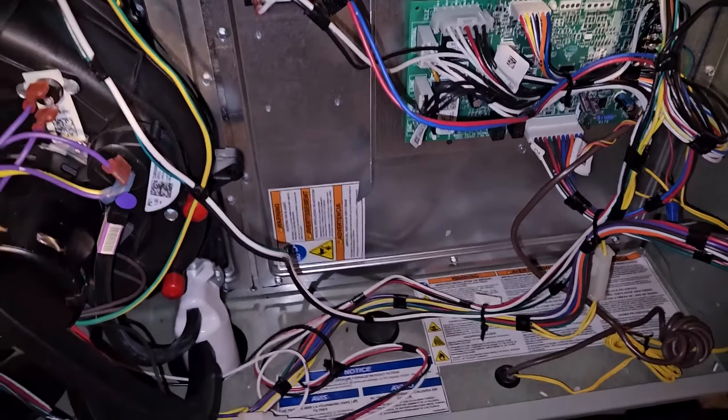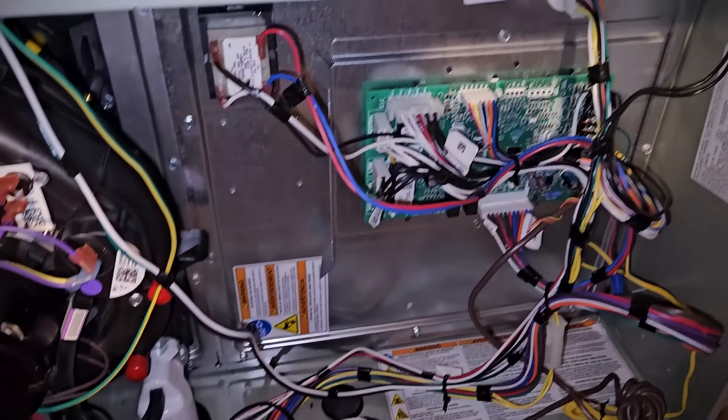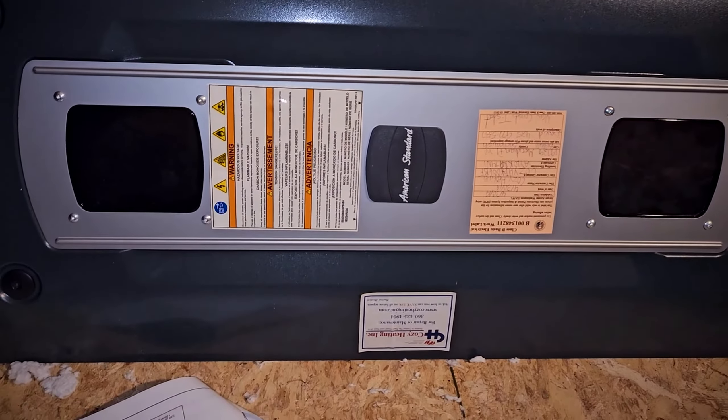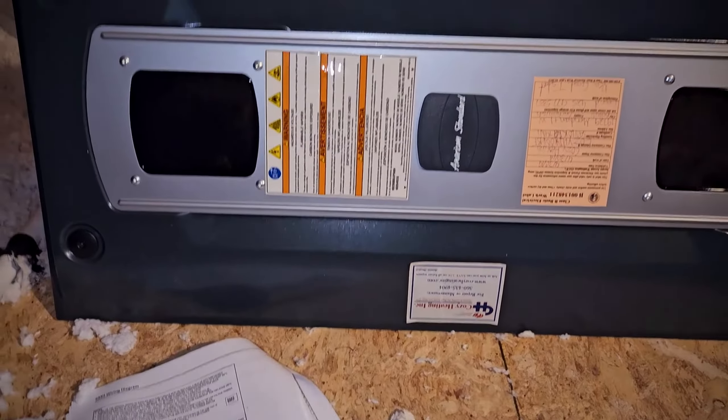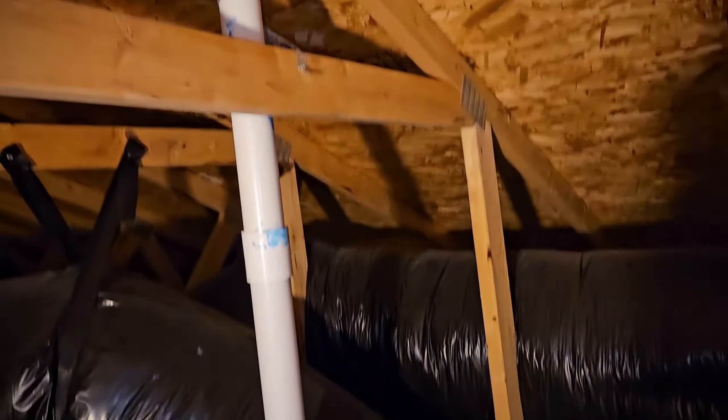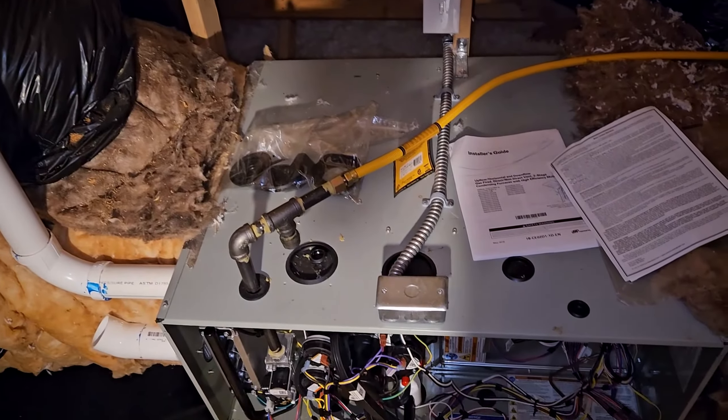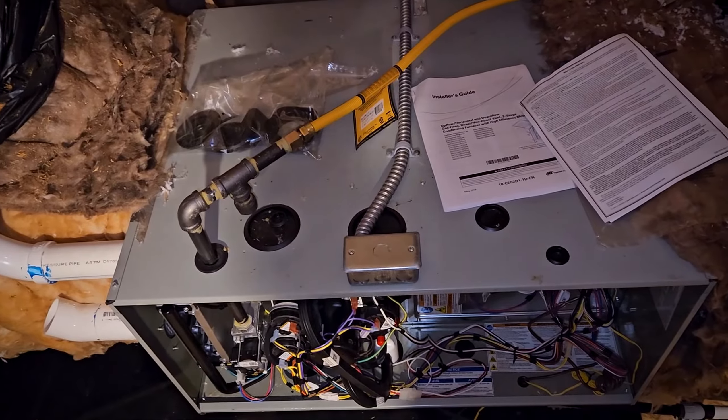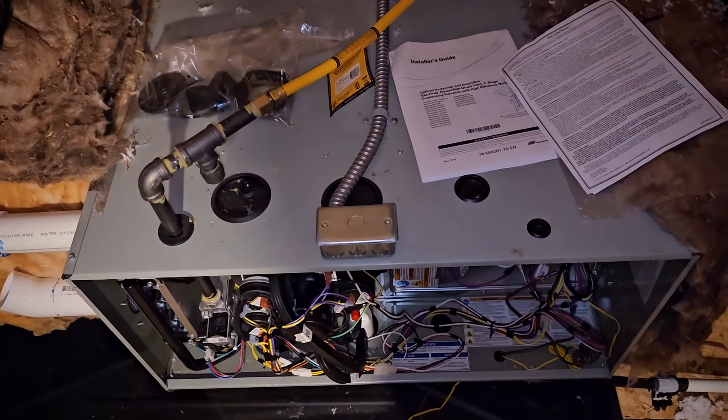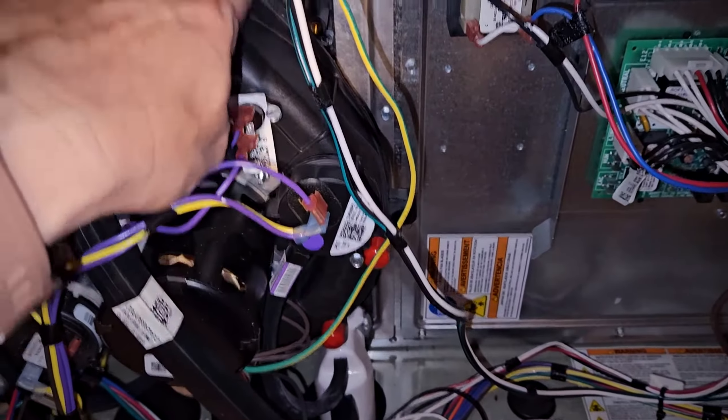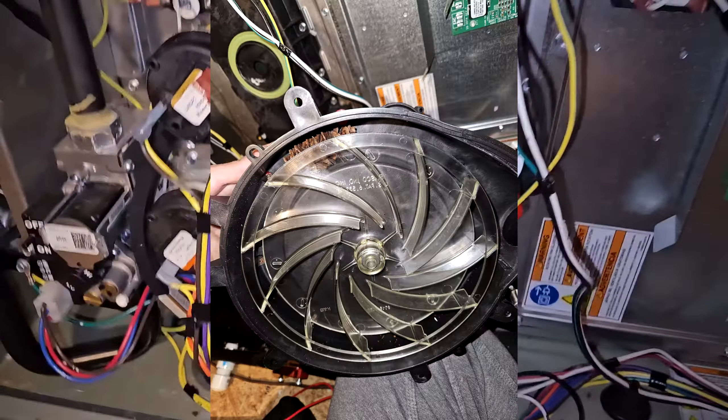All right guys, I just went through a learning experience on this furnace. It is an American Standard high efficiency, and the problem was that I almost never use this thing, but I just turned it on and it was not starting. It ended up being a little pine cone that got stuck in this motor.